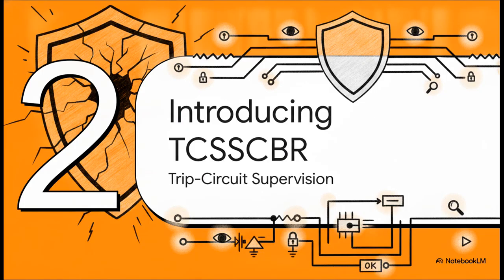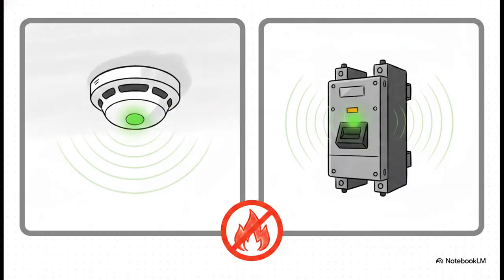Section 2. Introducing Trip Circuit Supervision. That terrifying gap in our armor is exactly why we need a dedicated function to watch the wire itself. Think about a smoke detector in your house. Waiting for a massive fire to break out just to see if the alarm actually works is, well, obviously a terrible idea, right? You need to know it's ready before the smoke appears. That's why smoke detectors have that tiny continuous green power on light. It doesn't wait for a disaster, it constantly proves its readiness. TCSSCBR is basically the continuous green light for your substation breaker.